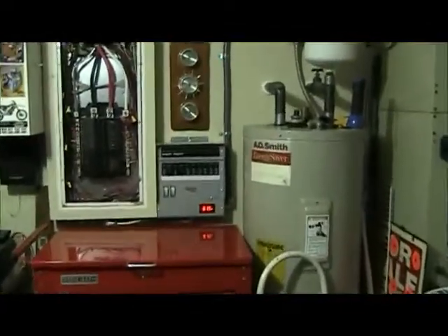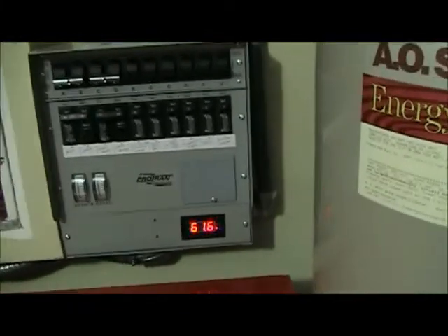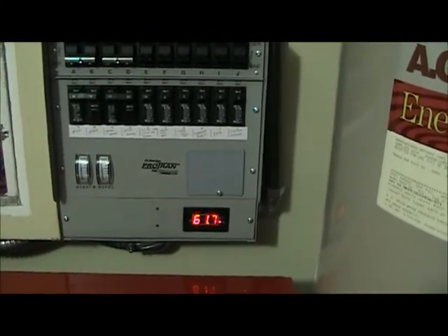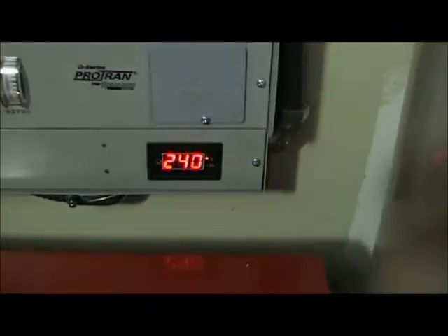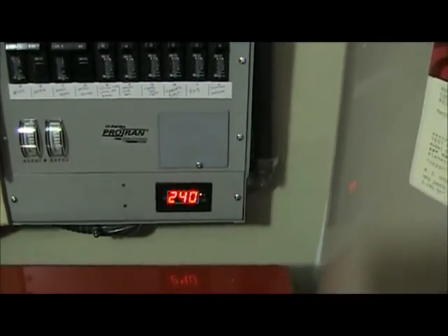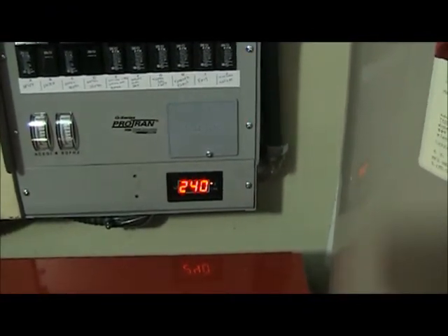Pretty noisy, hard to hear there. I showed you a DC amp meter down next to the generator that shows excitation current, and there's also a voltmeter that just reads AC voltage. Here in the garage I have a transfer panel, and now it also shows at the bottom another one of these digital readout deals that shows me the frequency and the voltage. So I have a perfect 240 volts and about 61.67 hertz.